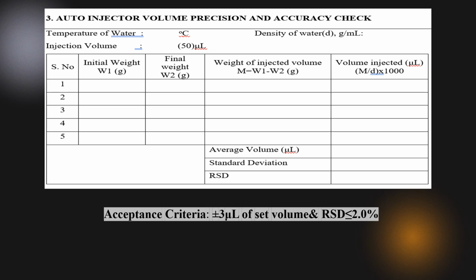Now the third part that needs to be calibrated in HPLC is your auto injector. Okay. So how are you going to do this? You're going to fill the vials with 1 ml of your liquid, that is water, and you're going to note down the initial weight, and you're going to inject 50 µL from that vial, and then you're going to take the final weight. So W1 minus W2 is going to give the weight of injected volume. So the volume injected is going to be the weight of injected volume divided by the density of the water into 1000. So it should give you 50 µL.